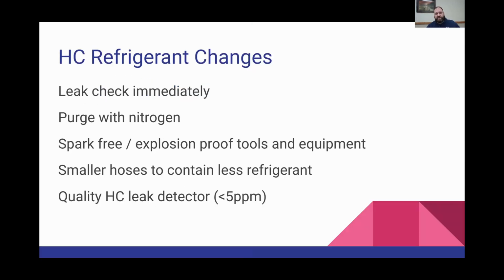Now, there are some additional requirements with these, like if you think you have a leak, you should be leak checking immediately with something that's going to pick up 5 parts per million so that you don't accidentally have a little combustible flame on your hands. You still need to purge with nitrogen, so having a really good nitrogen regulator. You also need to have spark-free or explosion-proof tools. So our equipment that we're using to service this needs to be rated for that. They even go as far as to say if you're working in a confined space, you may need approved ventilation, so fans and things of that nature. And then typically HC refrigerants use a much smaller hose to access it so that you have less of it available. So those are some things related specifically to the hydrocarbons.